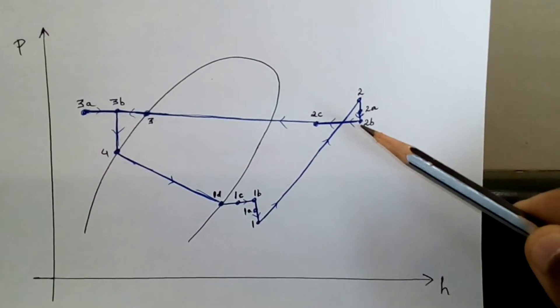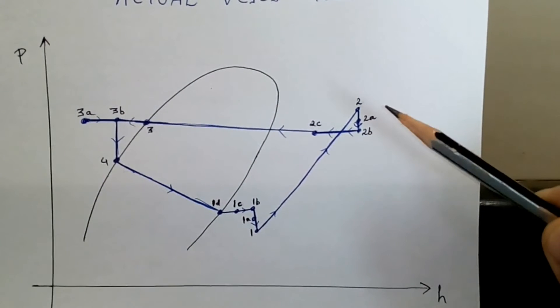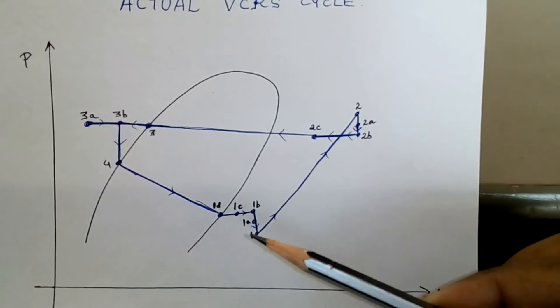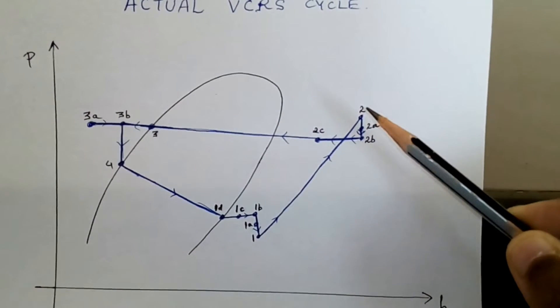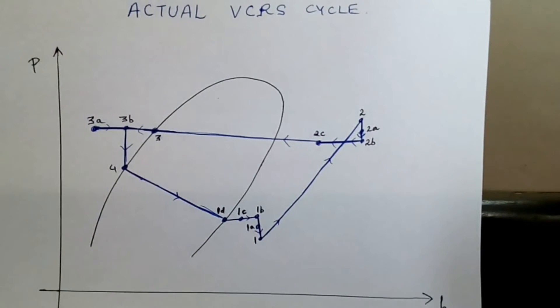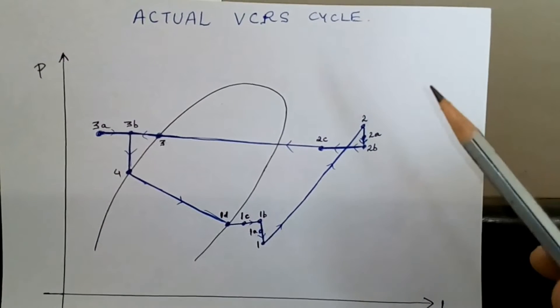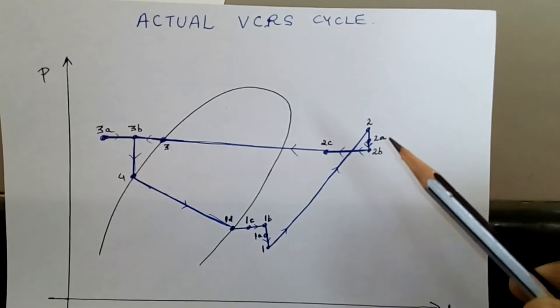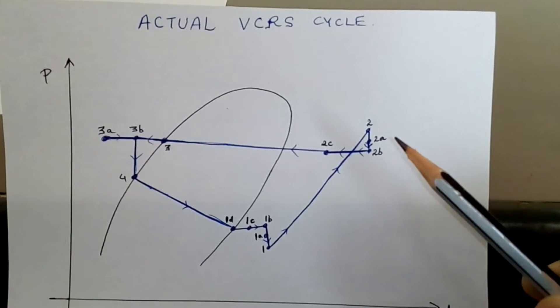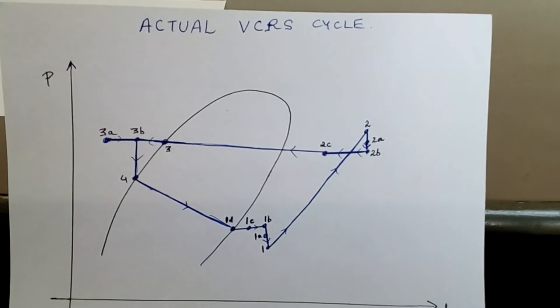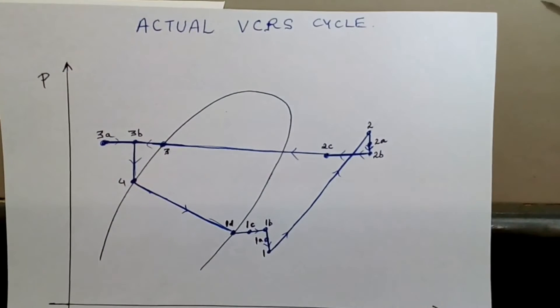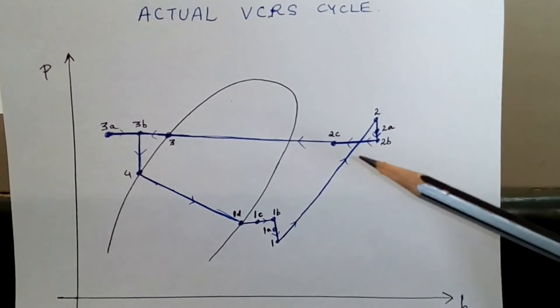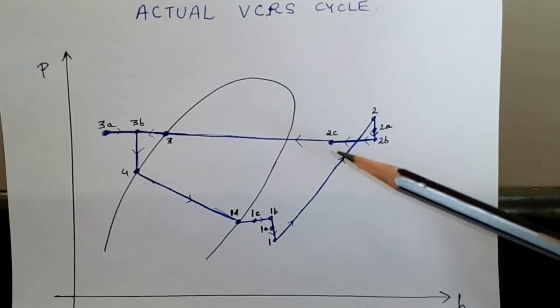From 2 to 2a there is a pressure drop at the exit valve of the compressor. From 2a to 2b there is a pressure drop in the delivery line. From 2b to 2c there is desuperheating, where heat is removed.